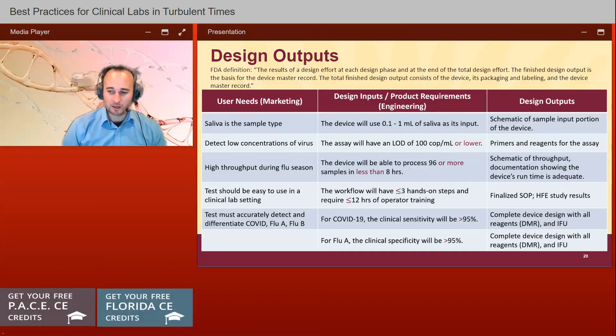Another user need could be that it's easy to use for your lab staff in a clinical lab setting. So your design input, okay, the workflow will have less than 3 steps and require less than 12 hours of operator training. We're getting specific. We're getting quantifiable here. I can actually verify that I've met this by making a finalized SOP and doing some human factors engineering studies, and then showing those results as my design output. So those are some examples of design outputs to verify your design inputs.